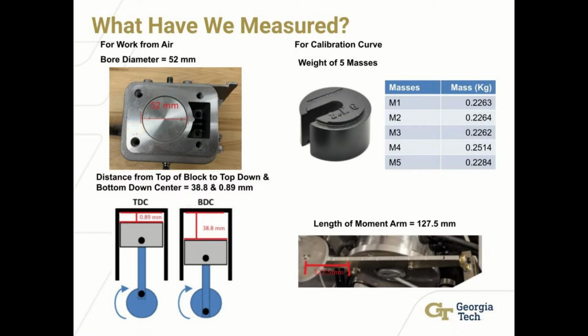The bore diameter was measured with a caliper for the work of air term, and it was 52 mm. Each of 5 masses was measured for the calibration curve, as shown in the table. The distances between the top-down and bottom-down center in the top-up block were 38.8 mm and 0.89 mm respectively. The length of the moment arm was 127.5 mm.